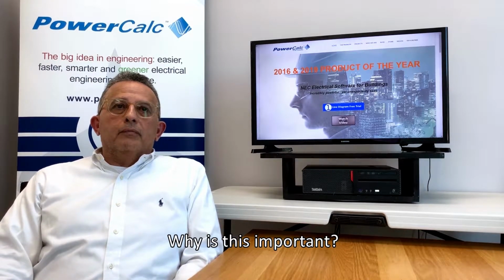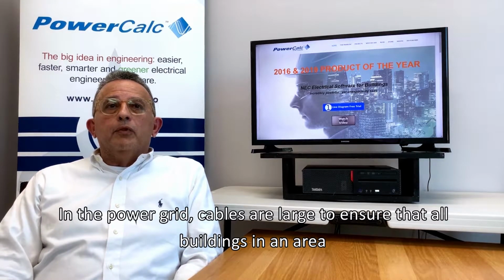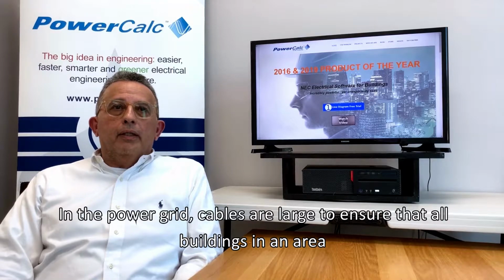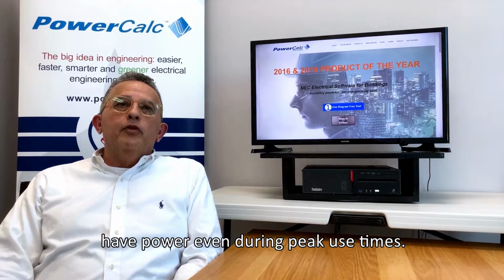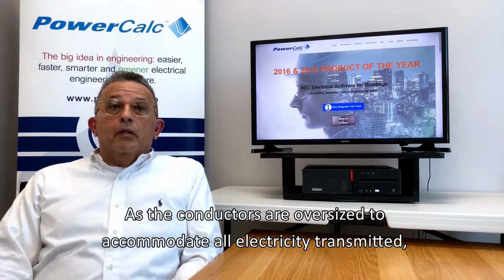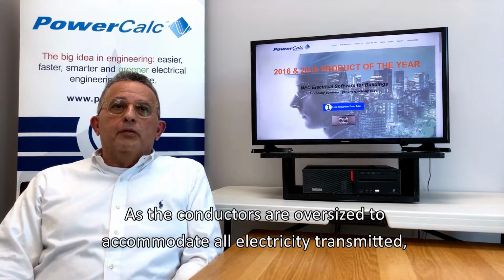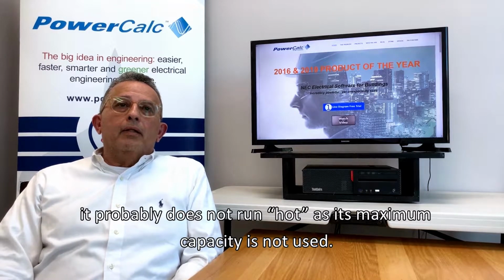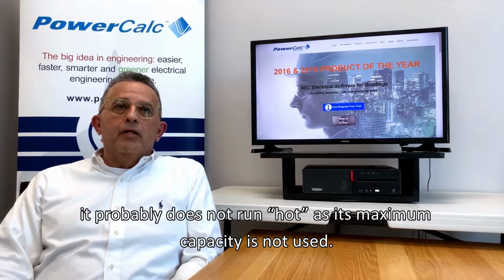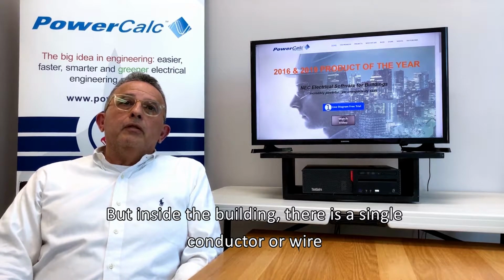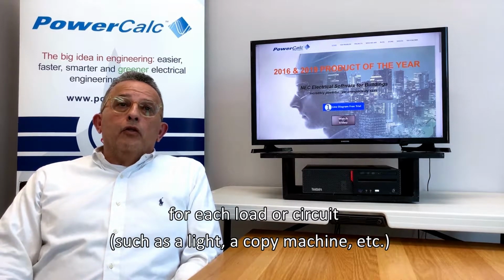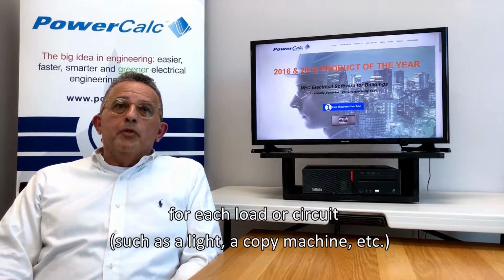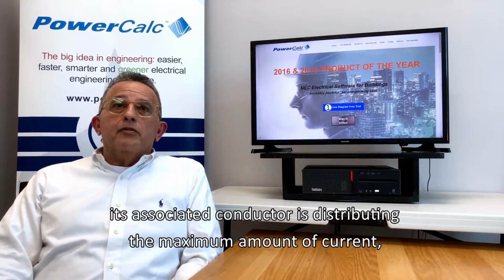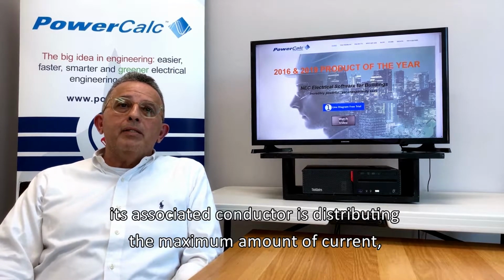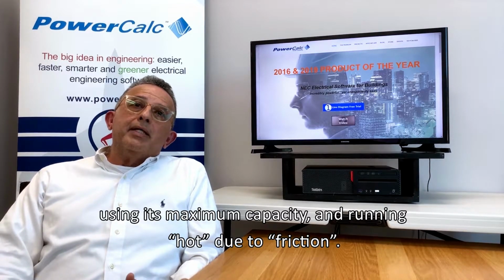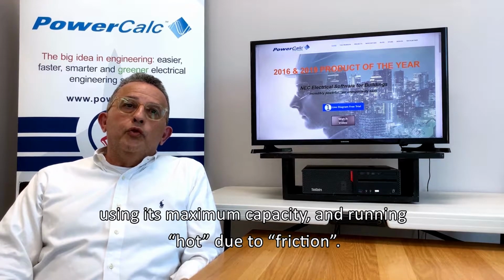Why is this important? In the power grid, cables are large to ensure that buildings in any area have power even during peak use times. As the conductors are oversized to accommodate all electricity transmitted, they probably do not run hot at maximum capacity since that capacity is not fully used. But inside the building, there is a single conductor, a wire, for each load or circuit, such as a light or a copy machine. When a light is on, its associated conductor is distributing the maximum amount of current, using its maximum capacity and running hot due to friction.